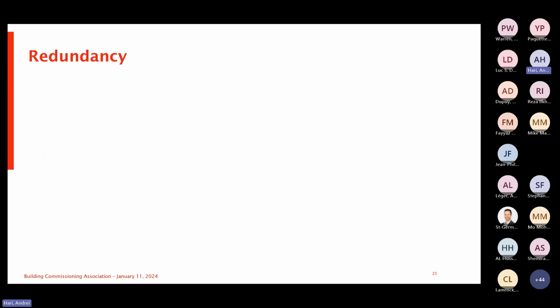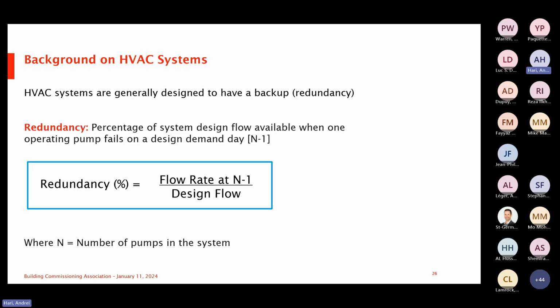And then lastly, redundancy. One of the other challenges in our industry is that engineers typically design their systems for 100% redundancy. That means we're going at an N+1. So we have 1 pump that is designed to do 100% of the flow, and then a second unit that's there as an idle asset. When we look at redundancy, though, maybe it's easier to have 2 pumps operating in parallel, make the sizes slightly smaller, and determine the actual amount of backup that you need in your system.